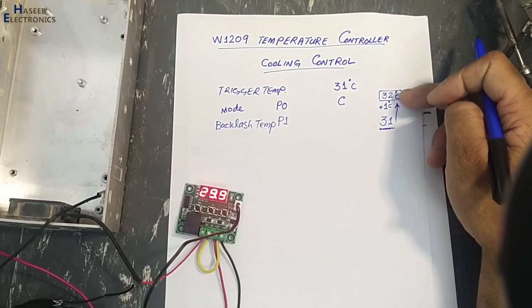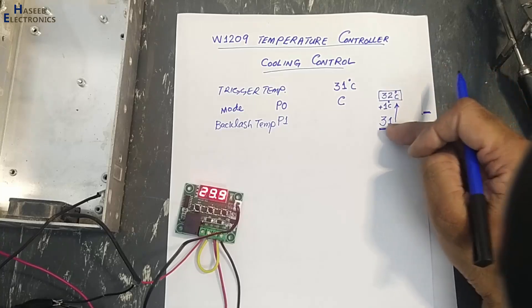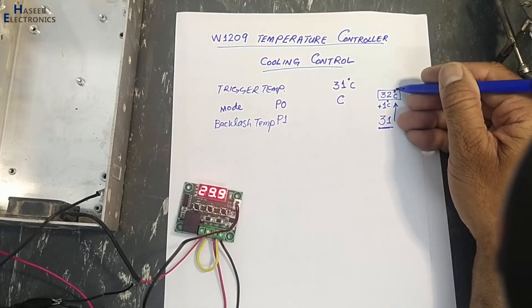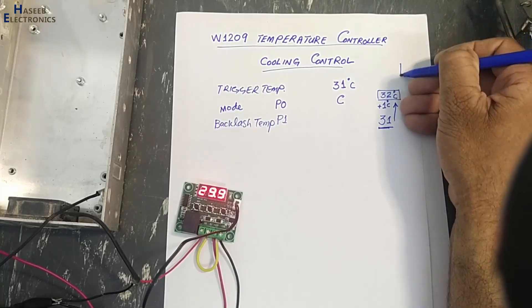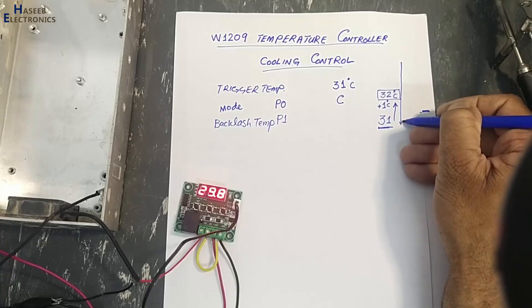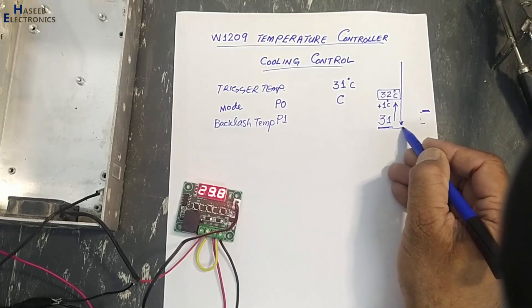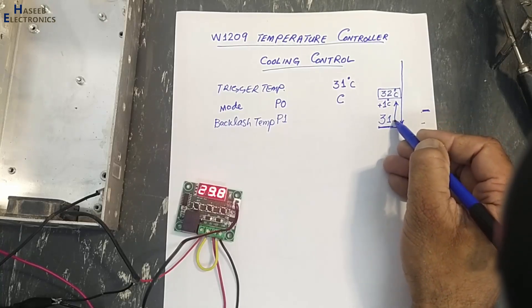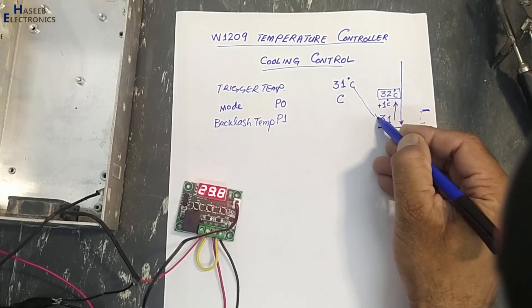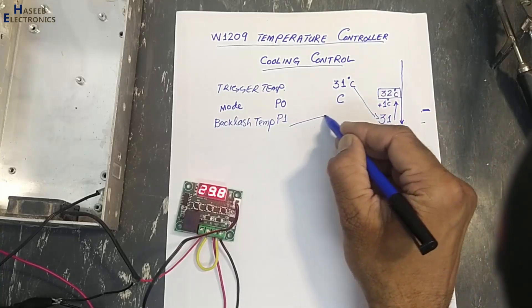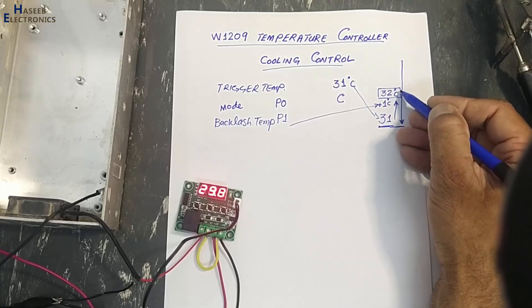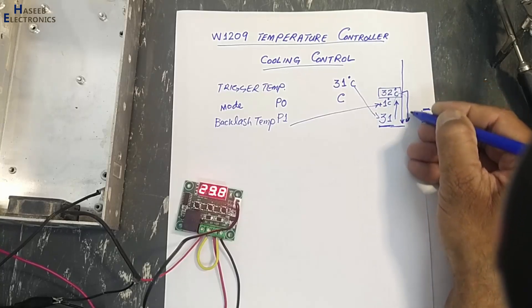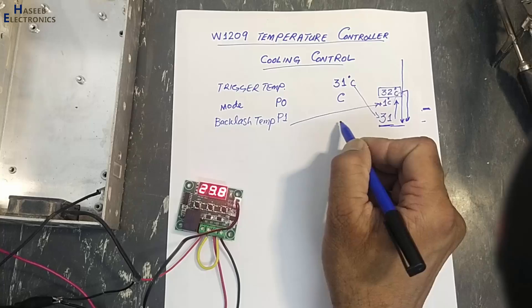When the temperature increases from 31°C to 32°C, it will start the compressor, blower, or fan to decrease the heat. When the temperature decreases back to 31°C, it will disconnect the fan or compressor. When it rises again to trigger plus backlash temperature, it will activate cooling again — so this cooling cycle keeps running.